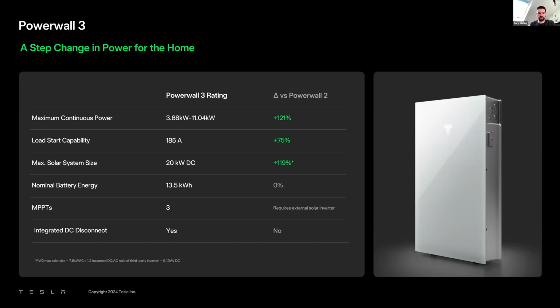The solar inverter built into Powerwall 3 has 3 strings, giving you tons of flexibility. You can go as low as 2 panels per string and as high as 15.